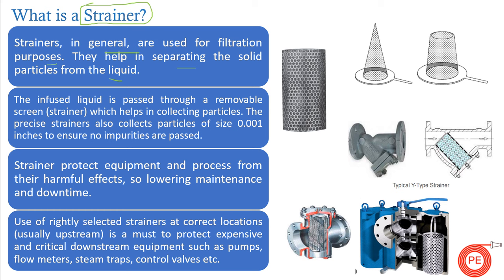The infused liquid is passed through a removable screen — this removable screen is basically what we call a strainer. This helps in capturing particles, which can be as small as 0.001 inches. Depending on the type of fluid moving through the screen, we have different mesh sizes. You can see in some pictures the holes are bigger, while in others they are very tiny — the mesh size is selected based on the solid particles present in the network.